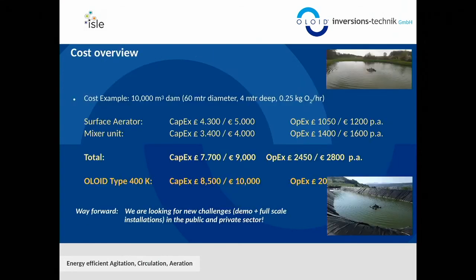I also have a cost overview comparing options for pond treatment plants. Normally running a surface aerator and a mixer together has a total investment cost of around 9,000 euros or 7,700 pounds, with operating costs for energy and maintenance of around 2,450 pounds per year. Our investment price is slightly higher due to our small production scale, but the machines typically achieve return on investment in 3 to 4 years, which is quite good for wastewater treatment plants.